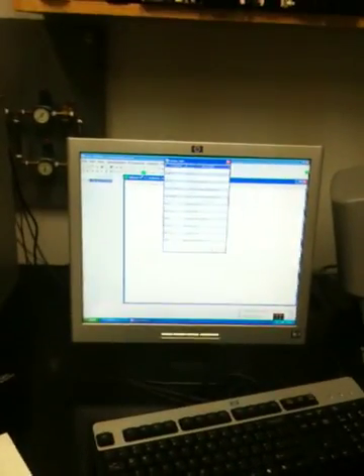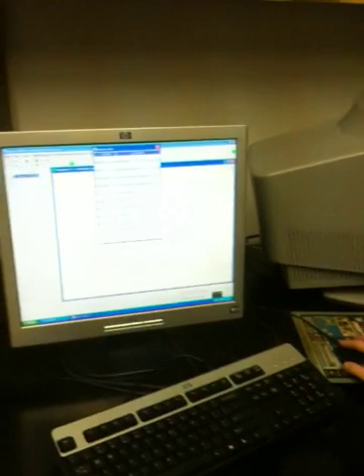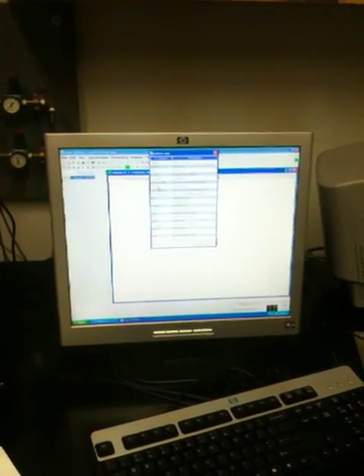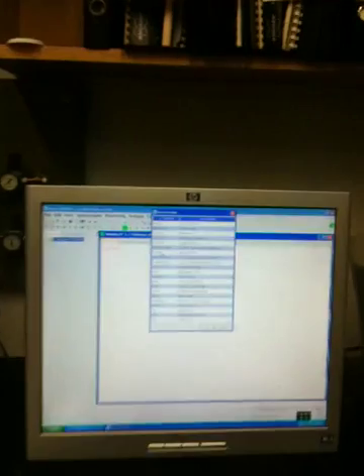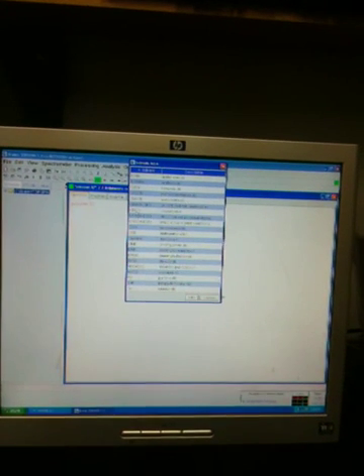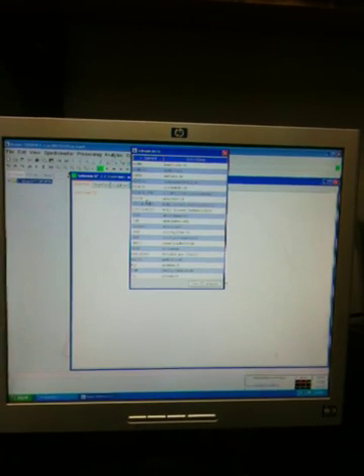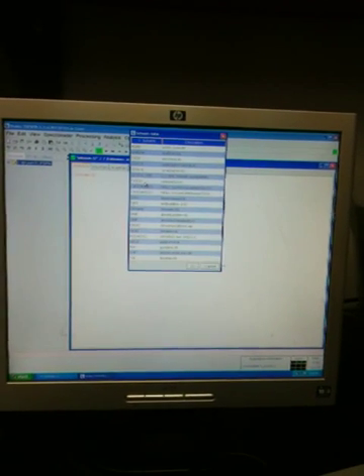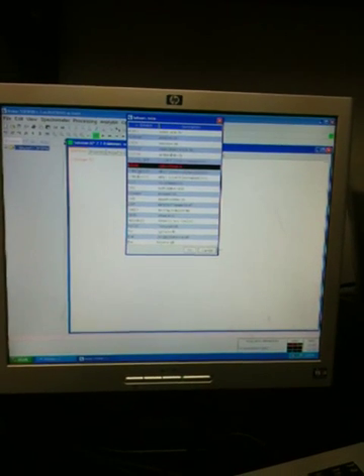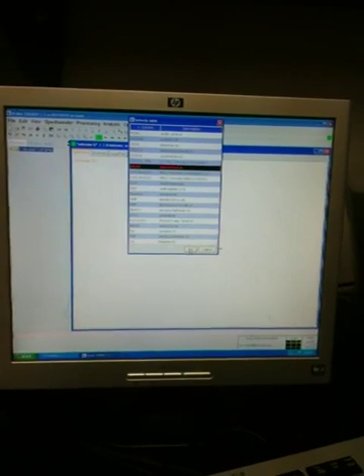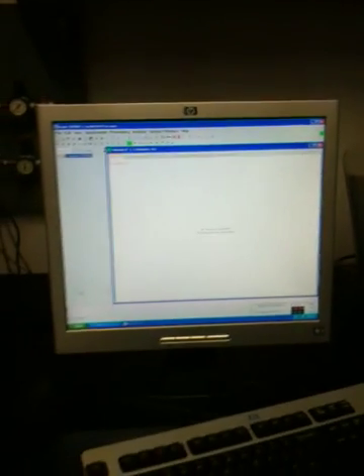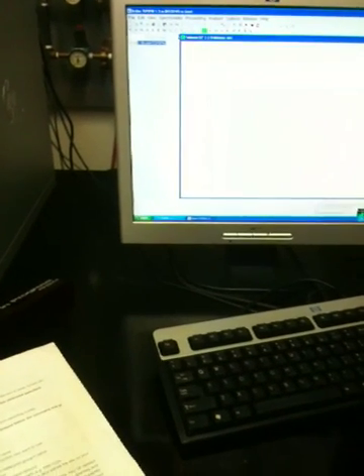I'm going to type lock. When I type lock, I once again have to tell the instrument what solvent I'm using. And the solvent I'm using is CDCl3. This is deuterated chloroform. That's what you mixed in with your sample. Clicking on that. Clicking okay. Now I'm going to type lock disc.